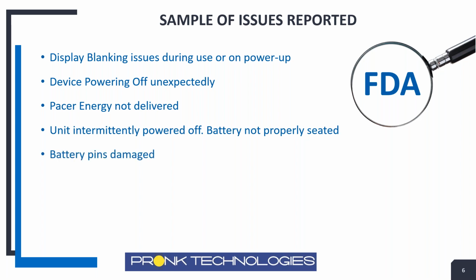There were other issues reported where the battery pins on the defibrillator or the battery itself were damaged in a way that was causing intermittent operation on battery power. So imagine that you're talking about somewhat of an accessory. It is integral, but it's an external component. And if those battery pins are damaged in a certain way, it can cause the device to power off when you need it, particularly in the field where you're commonly using it on batteries.